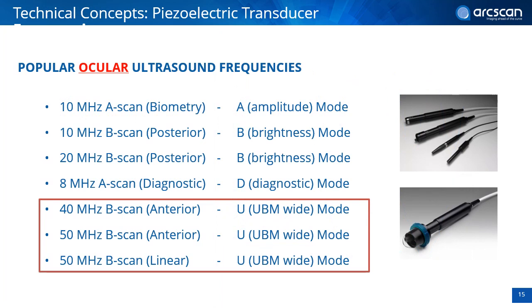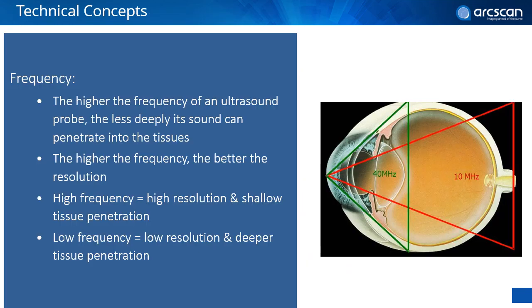For ultrasound of the eye, we use different frequencies depending on the area of the eye we're examining. The most popular ones are those that you have here on the screen. Generally, 40 and 50 megahertz frequencies are used for anterior UBMs. How does the frequency affect the image in the eye? Well, the higher the frequency is, the less penetration into the eye, and the greater the resolution. When we're using ultrasound in the eye, we're balancing penetration, that is, how deeply can we get an image, with really good image resolution. So you can see here that a 10 megahertz is going to image really deeply inside the eye, but it will not have the resolution that we want or need for the cornea as an example.